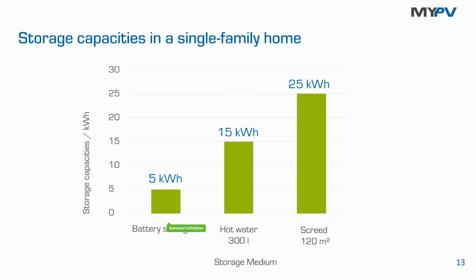We see another option at MyPV. We see the hot water boiler or the storage tank as another application for excessive power. And see there, if you heat up the hot water volume of a 300-liter boiler, let's say to 45 degrees centigrade, then we can use 15 kilowatt hours of your own produced solar electric energy. And this is many times more capacity, of course, and this capacity is already there. It's already there where people live in residential buildings, and we can make use of this storage capacity.